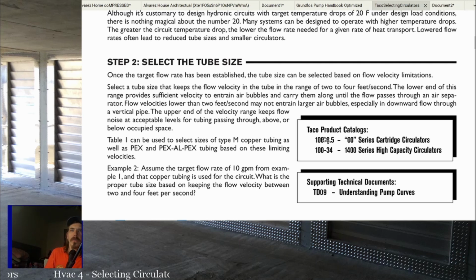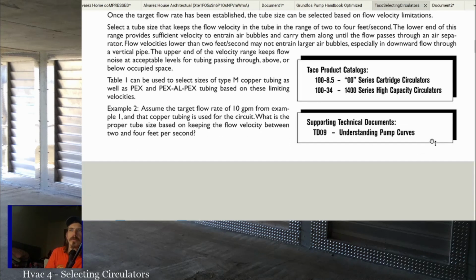So table 1 can be used to select sizes of type M copper tubing as well as PEX and PEX-AL-PEX tubing, based on these limiting velocities. Example 2: assume the target flow rate of 10 GPM from example 1, and copper tubing is used for the circuit. What is the proper tube size based on keeping the flow velocity between 2 and 4 feet per second?